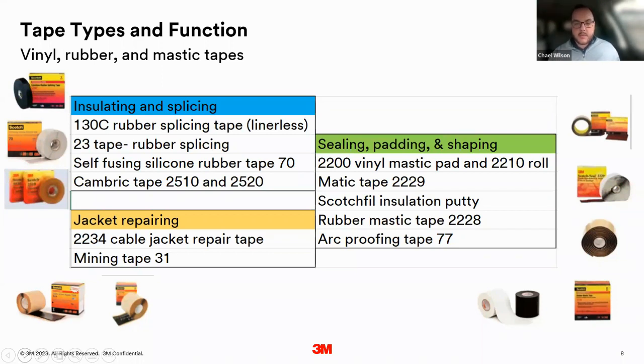That includes our mastics. We have a number of different kinds of mastic tapes. And really what mastic tapes are is a putty, less of a tape and more of a putty that's been put in the shape of a tape. Basically, if you wrap a mastic around a cable or whatever you're doing to give it that moisture protection, when it comes in contact with itself, it forms to itself and becomes one solid object. The advantage of that is that there's no seam where moisture or dirt or anything is going to get under that seam and damage your cable underneath. It becomes one solid object, so there's really no leakage or anything there if it's applied correctly.